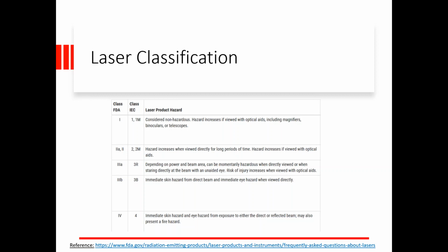So the main hazard with an Erchonia laser is optically. Obviously, that's why we include safety glasses with our devices, because you never want to shine that laser directly in your eyes. There is that optical hazard in place. A class 3A laser, depending on power and beam area, can be momentarily hazardous when directly viewed or when staring directly at the beam with an unaided eye. Risk of injury increases when viewed with optical aids.